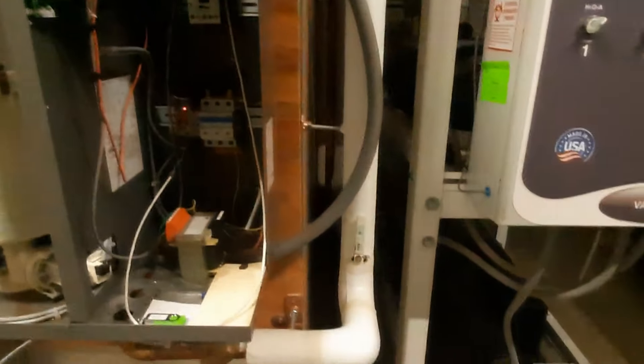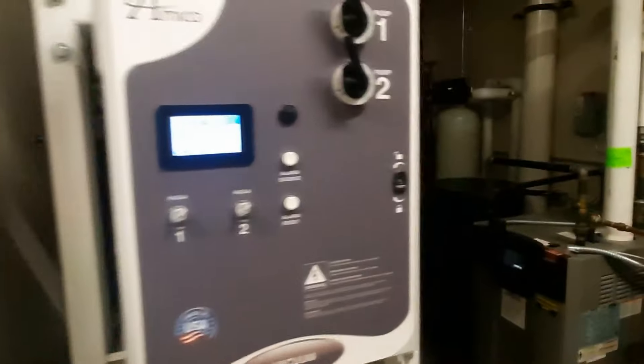We're gonna let this one go and watch it for a little while. Got a couple boilers, vacuum pumps, all kinds of good stuff in here, water softener back there. The water softener does not feed the steam humidifiers — that would cause a problem — and it looked like pretty clean water coming out. We've cleaned them out periodically over the last few months as we were trying to get them to make a move on the canisters. Still waiting on canisters; we'll do what we can here.